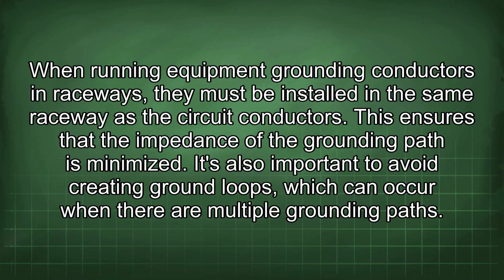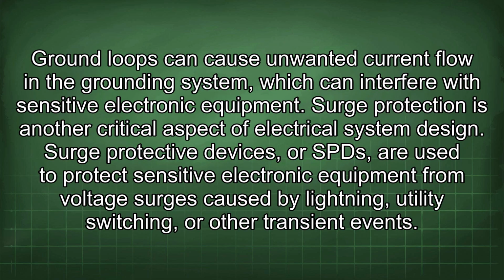It's also important to avoid creating ground loops, which can occur when there are multiple grounding paths. Ground loops can cause unwanted current flow in the grounding system, which can interfere with sensitive electronic equipment. Surge protection is another critical aspect of electrical system design.